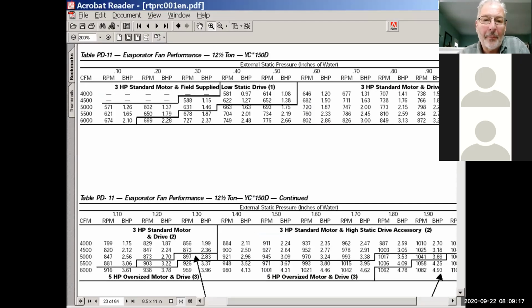But taking a static pressure reading is really important. Now, when you look at this 12.5 ton Precedent rooftop, when you look at the blower curve on these, it's like an eye chart. There's a lot of things to take in here, but a 12.5 ton unit, we need to get to 5,000 RPM, or excuse me, CFM. So in order to get there, we need to really kind of know what our static pressure is.